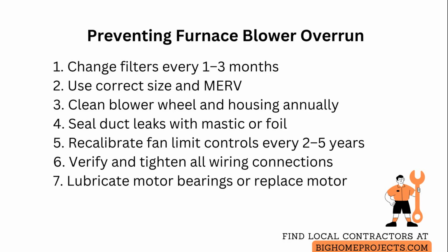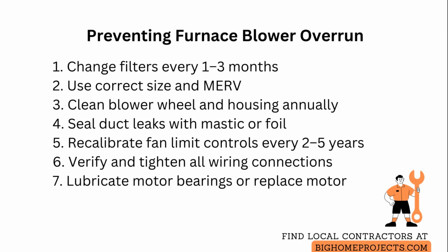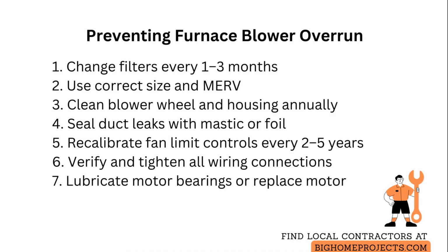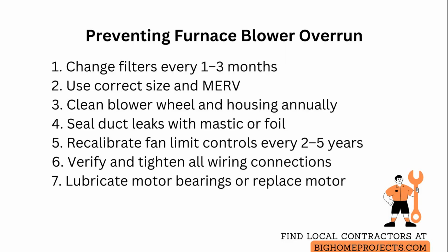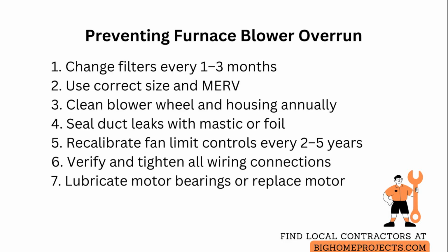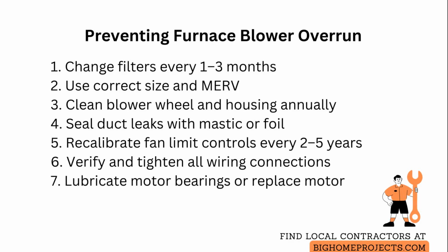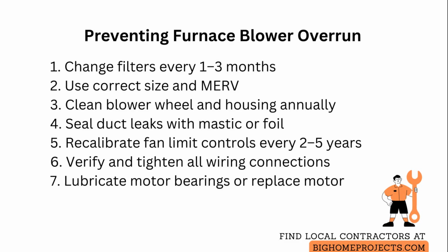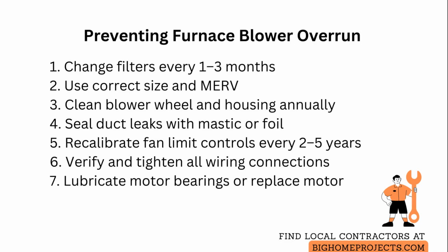Inspect ductwork for disconnected seams, crushed sections, and excessive dust and seal leaks with mastic or foil tape, while checking that return and supply grills are unobstructed to maintain proper static pressure. Recalibrate fan limit controls every 2 to 5 years by verifying the off and on temperature set points against the furnace operating temperature and adjusting the differential, so the fan starts only after the heat exchanger warms and stops after air has cooled, to prevent unnecessary runtimes.